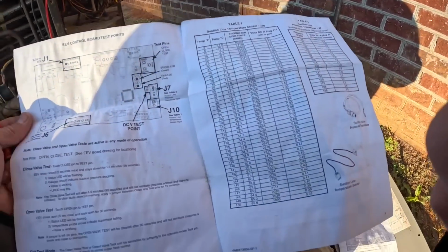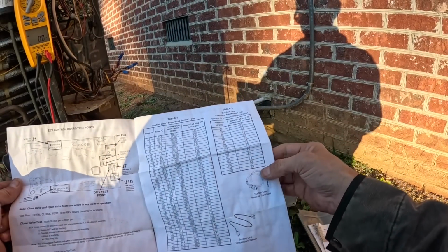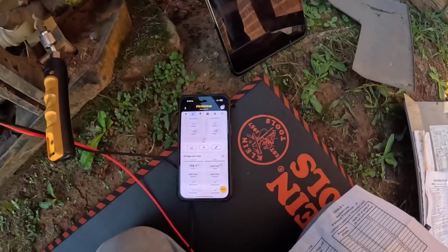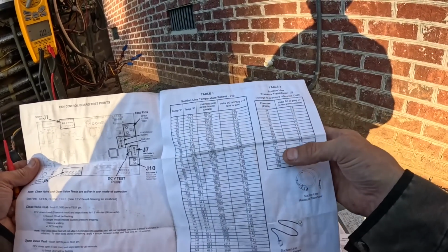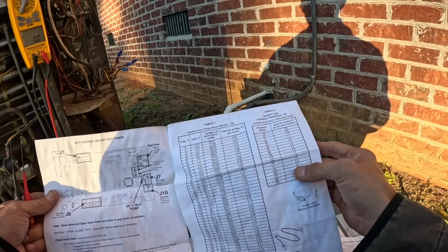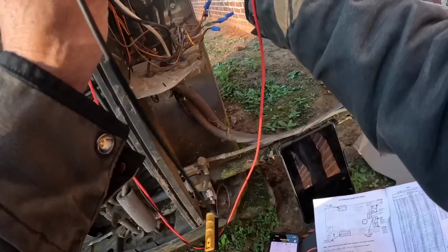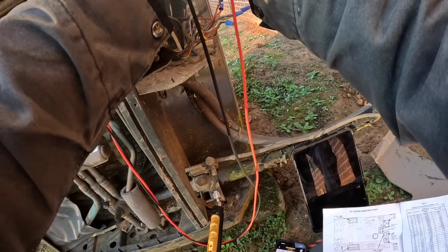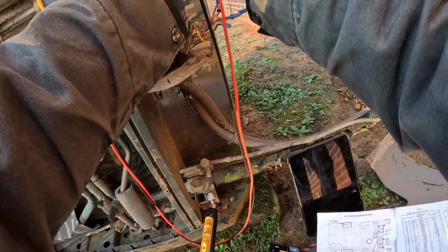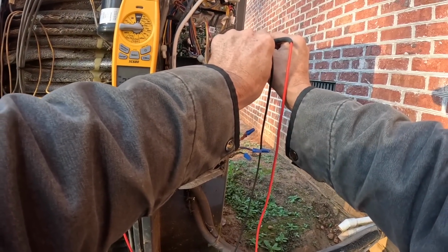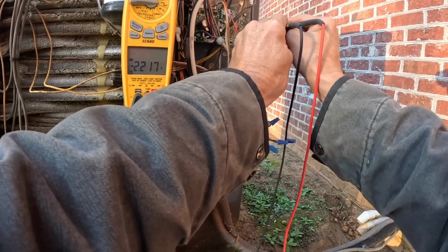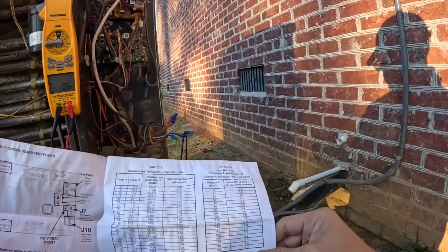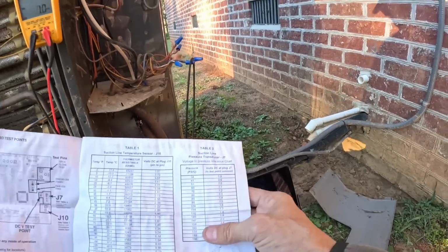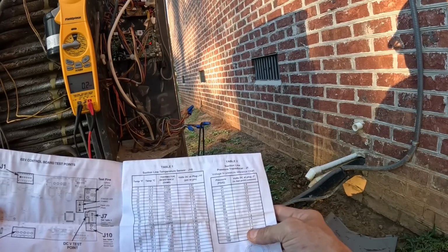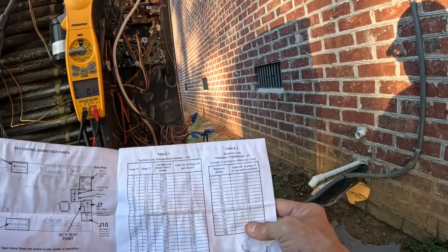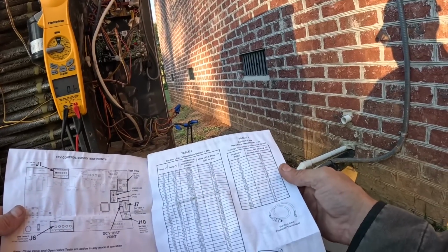All right, guys, some of the stuff that it says to test, we're going to test this pressure transducer here, or try to. We have a pressure of 155. So we should be getting something like 2 volts DC at J7. All right, there we go, 2.2 volts. And I said we were at 155.1. So it's reading just a little bit high, but I think that's within normal range.